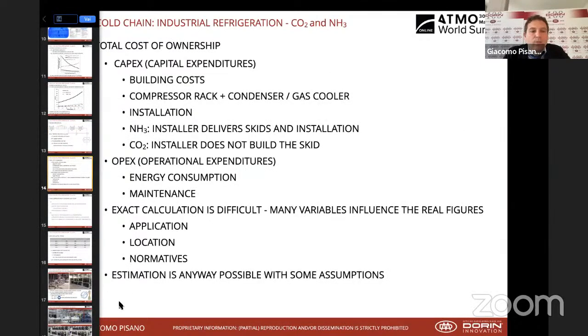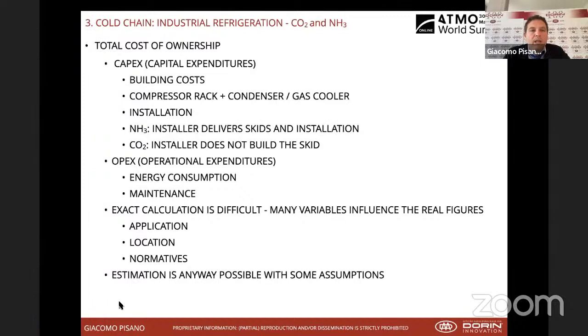When it comes to a comparison between CO2 and ammonia from a total cost of ownership, when it comes to capital expenditure, normally the compressor rack and the condenser or gas cooler is typically cheaper. Installation costs are cheaper. From an operational expenditure, clearly energy consumption is a driver. Definitely ammonia is a great refrigerant from a thermodynamic standpoint. So from a pure energy efficiency perspective, ammonia can be considered to a certain extent more efficient than CO2.